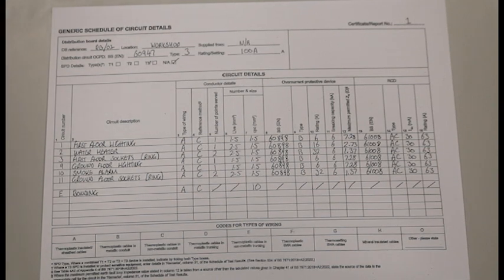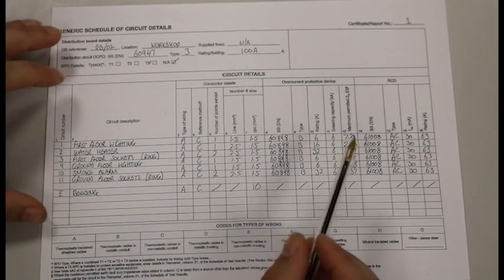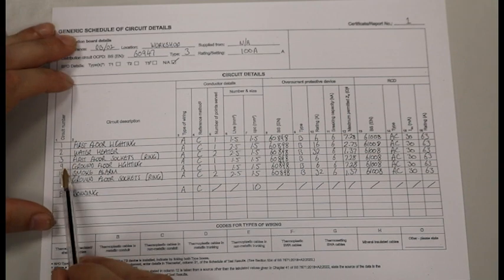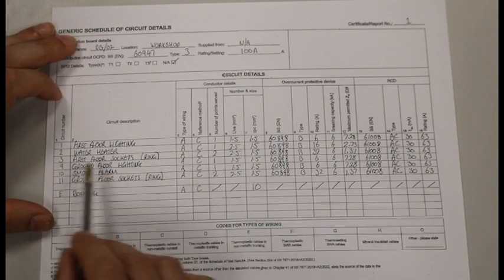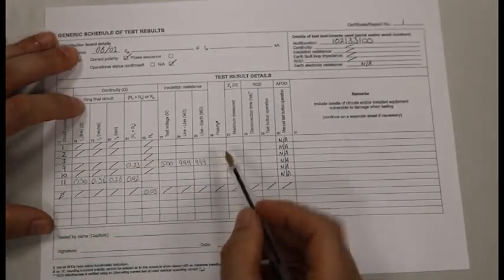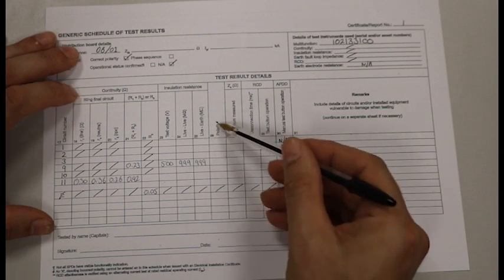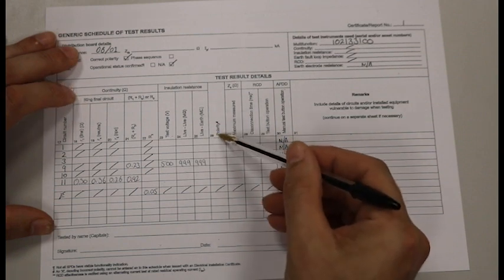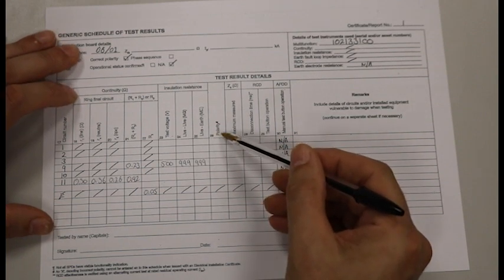Looking at the schedule of the test results for our polarity test, we were testing our ground floor lighting circuit which was circuit number 9. If we turn the page, we have circuit number 9, we go along to column 26 and it says polarity. So we checked polarity test A, B and C.